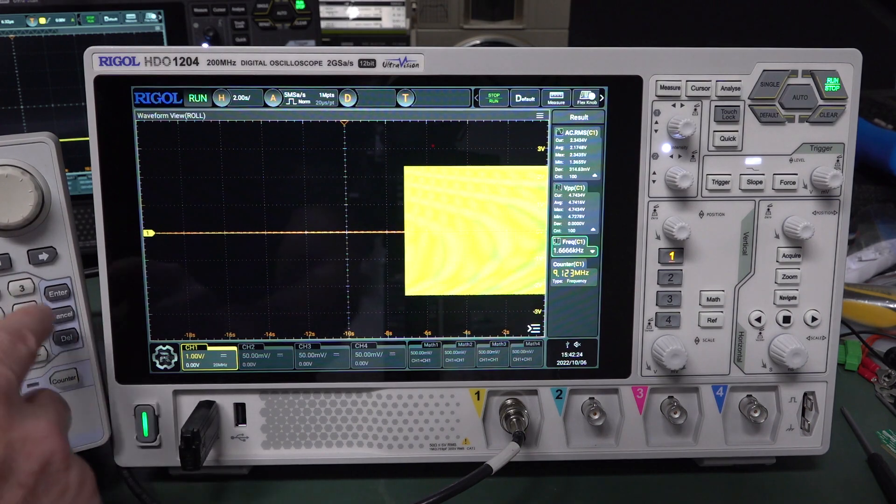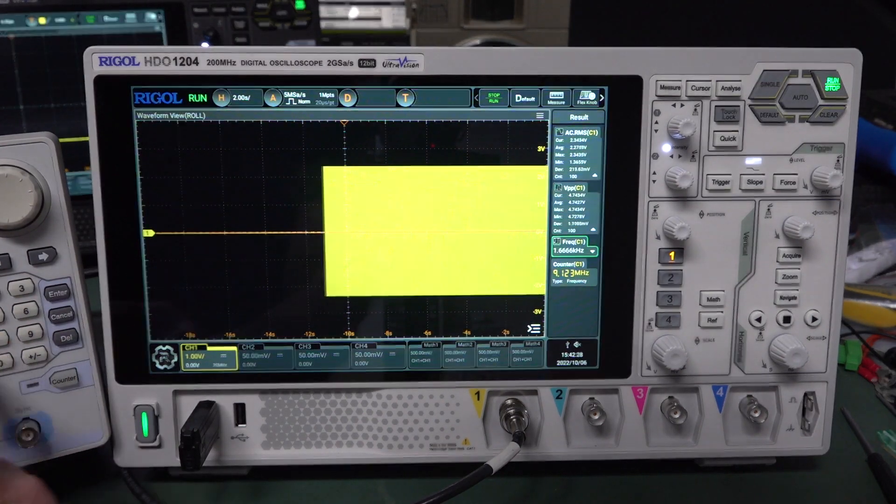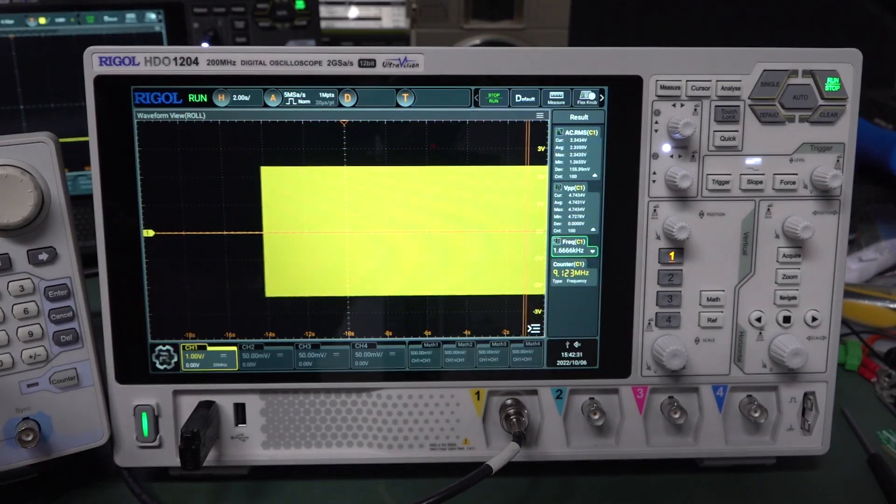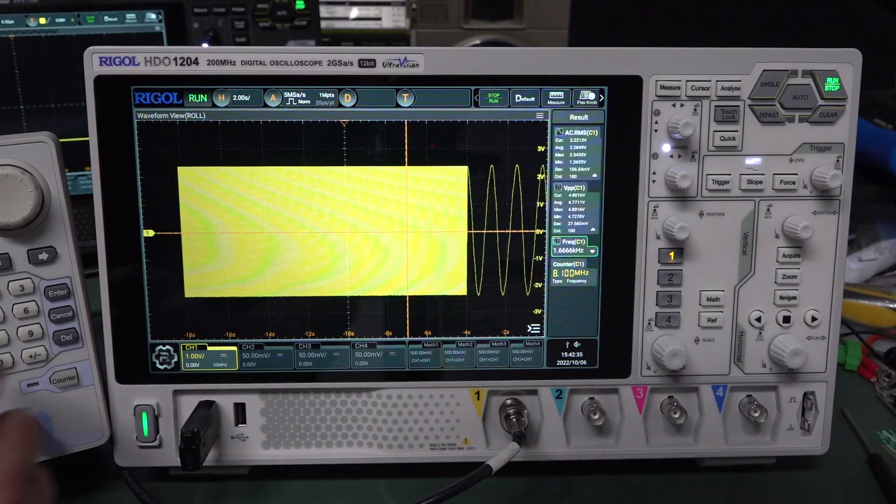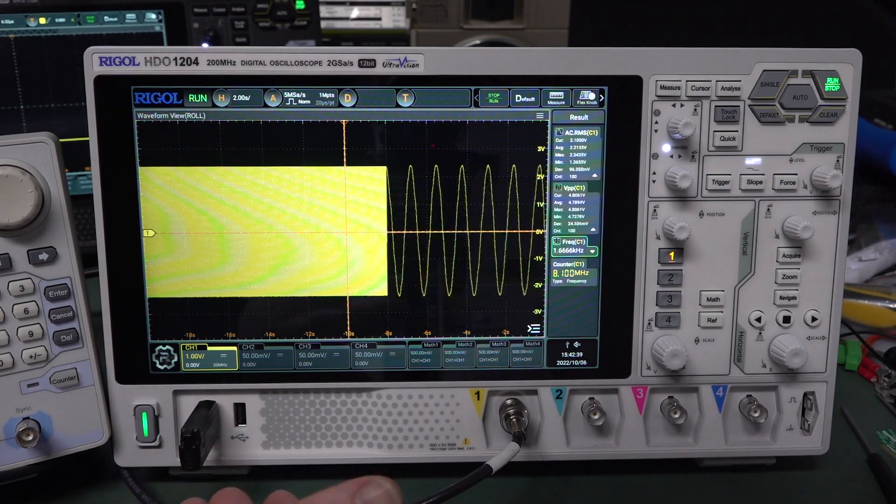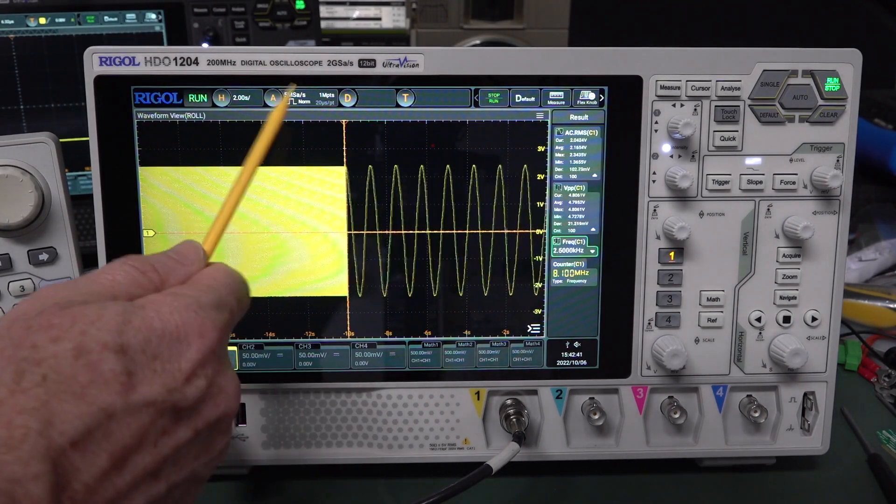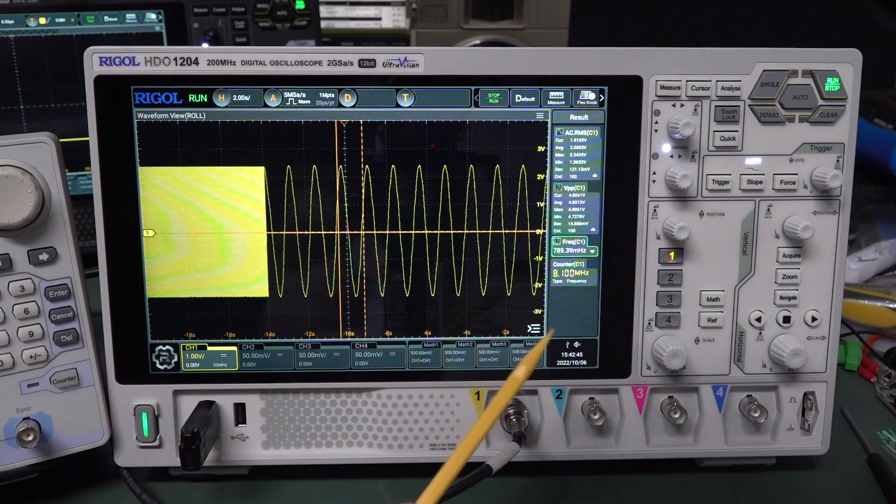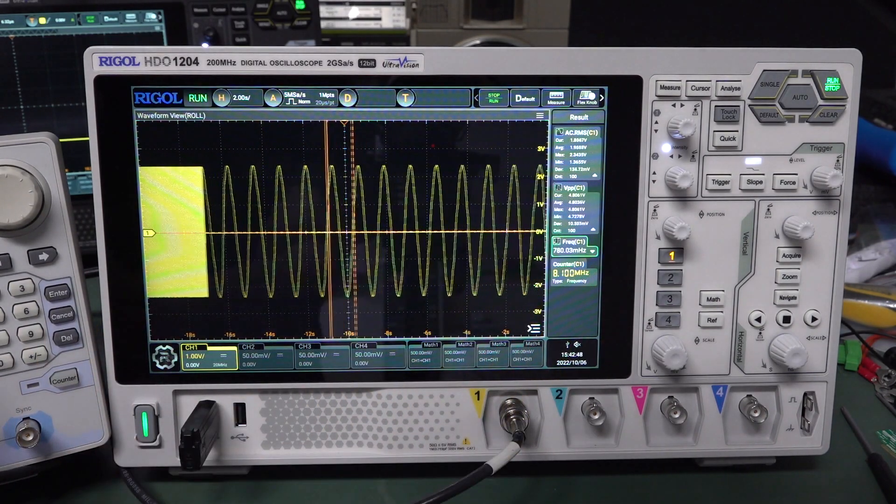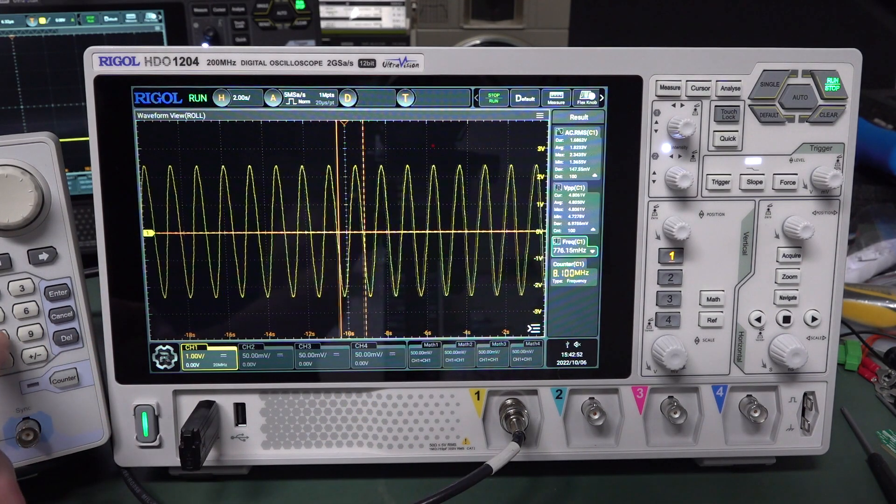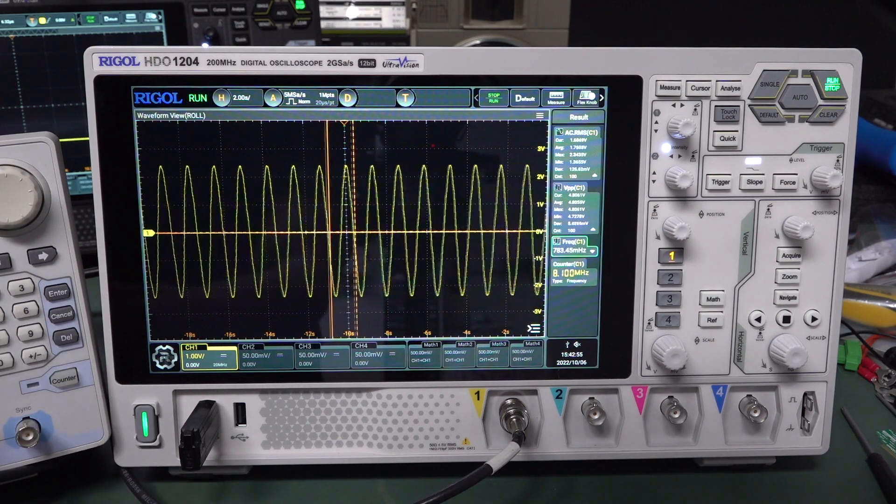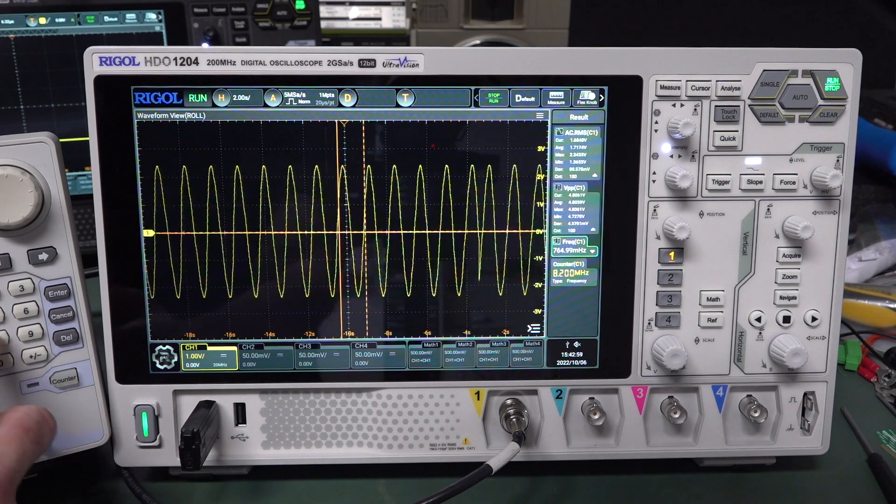So let's go to, I don't know, 8.1 megahertz. And boom, see? Instantly starts to alias. So what's 8.1? I don't know, get your computer out. 8.1, figure out why 8.1's doing it at 5 meg samples per second with 1 meg points. And 2 seconds, right? It's doing it. So 8.1, 8.2 megahertz. 8.2 megahertz is still doing it.